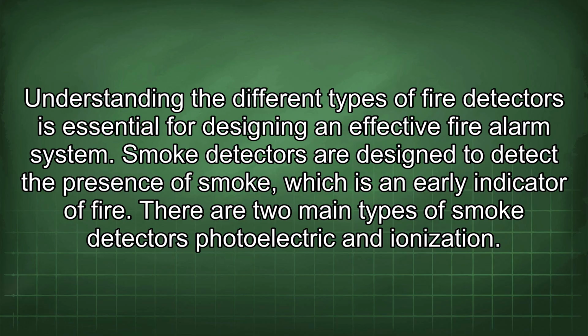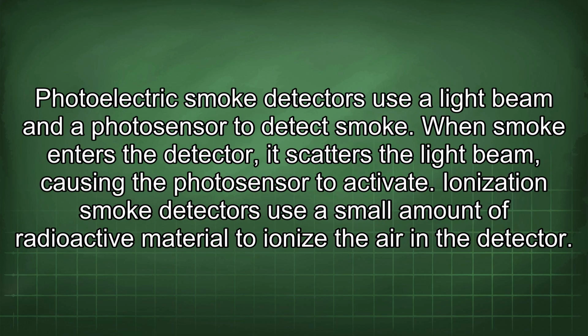Understanding the different types of fire detectors is essential for designing an effective fire alarm system. Smoke detectors are designed to detect the presence of smoke, which is an early indicator of fire. There are 2 main types of smoke detectors: photoelectric and ionization. Photoelectric smoke detectors use a light beam and a photosensor to detect smoke. When smoke enters the detector, it scatters the light beam, causing the photosensor to activate.